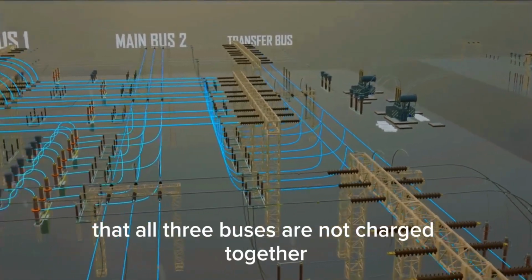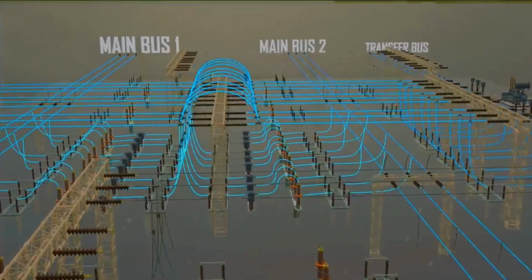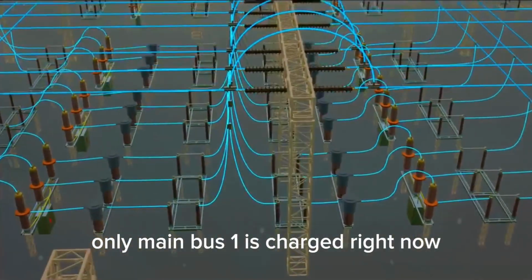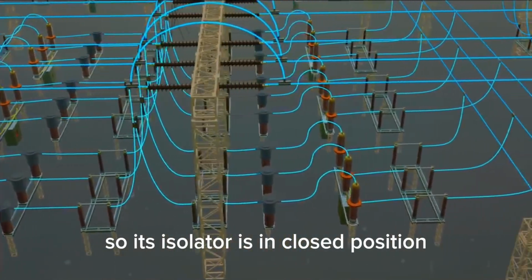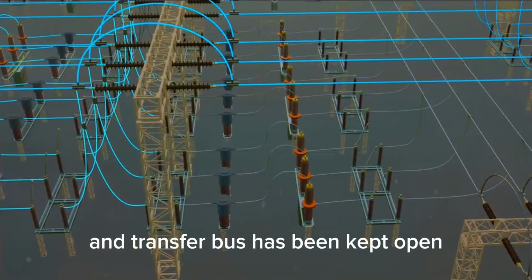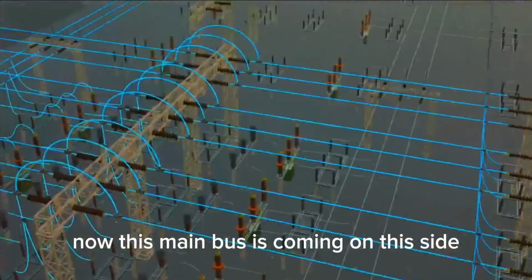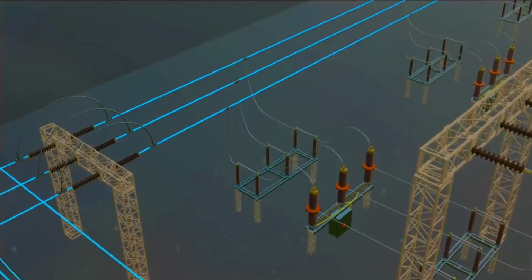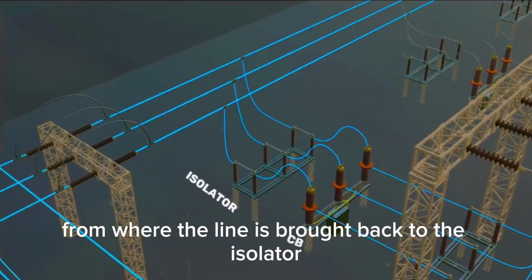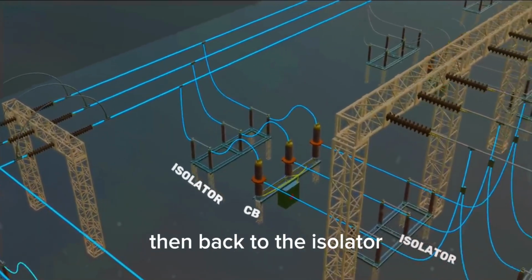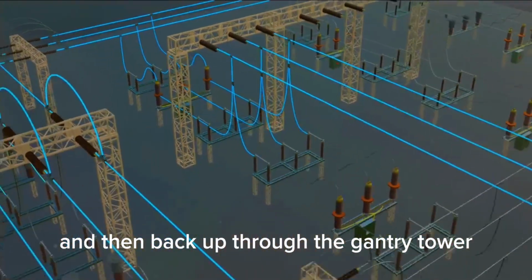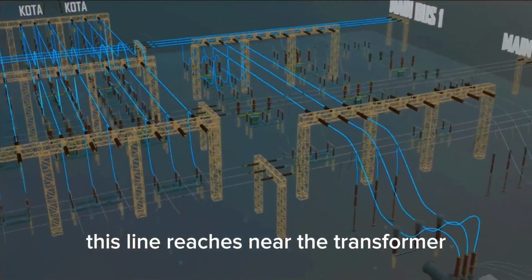But the thing to note is that all 3 buses are not charged together. Only main bus 1 is charged right now, so its isolator is in closed position. The isolator of main bus 2 and transfer bus has been kept open. Now this main bus is coming on this side, from where the line is brought back to the isolator and then to the circuit breaker, then back to the isolator and then back up through the gantry tower, this line reaches near the transformer.